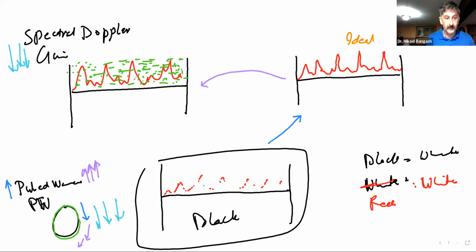This mainly means that you have increased the spectral Doppler gain too much. What this makes is similar to the confetti of your spectra that we had in the color Doppler. Or we can say that what it represents is noise.